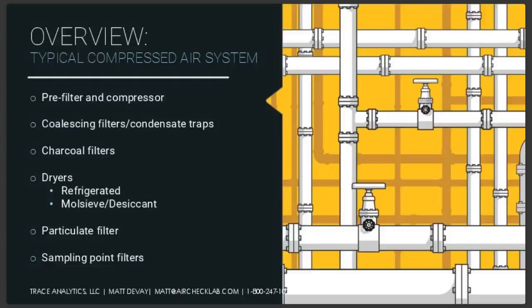Most systems these days have a pre-filter and a compressor where air comes in and is compressed to higher pressure. You have first stage treatment, which is primarily for condensates such as water and oil. The air typically goes to storage, not always. Upon demand, air will flow out of storage and typically goes through a few more condensate and organic vapor filtration. And then it goes to the drying step.